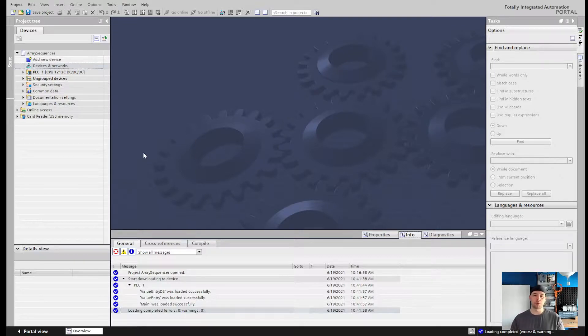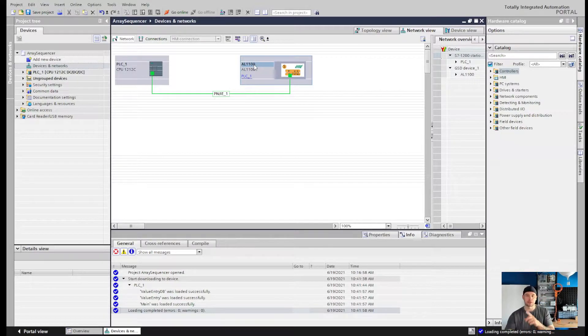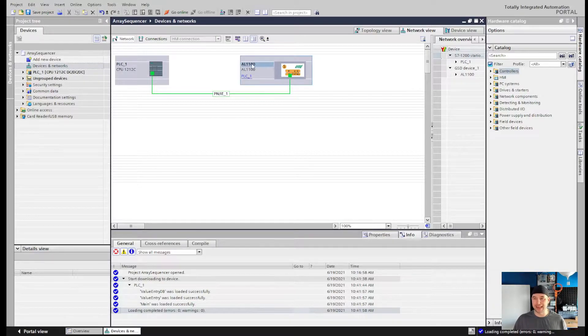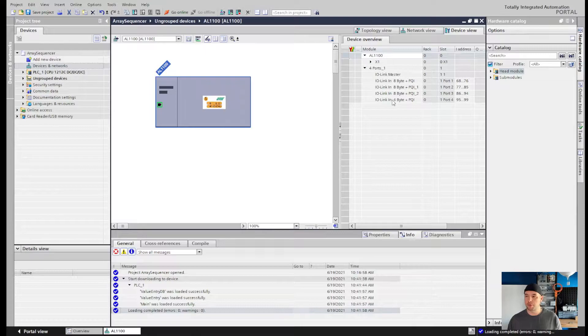We are back inside of TIA Portal. I've already set up this project but I'm going to walk you through the device setup and the program. Going into our devices, I have the S7-1200 and the IFM IO-Link master AL1100. If you're going to use this device, call IFM or check online because some are for Ethernet/Allen-Bradley and some are specific to Profinet — the AL1100 is Profinet-specific. Inside this device I have four sensors occupying four ports; three are analog distance sensors and one is an ultrasonic sensor.